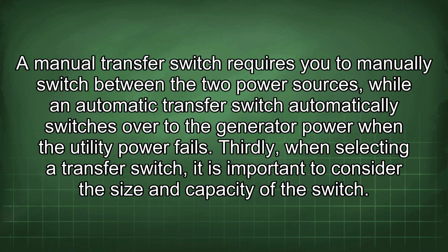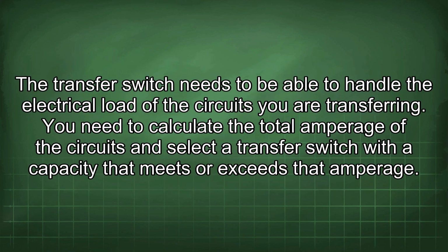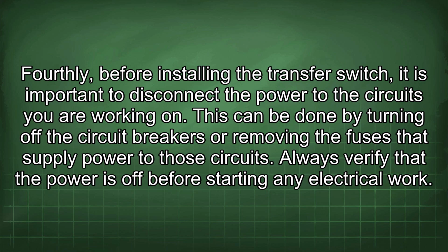Thirdly, when selecting a transfer switch, it is important to consider the size and capacity of the switch. The transfer switch needs to be able to handle the electrical load of the circuits you are transferring. You need to calculate the total amperage of the circuits and select a transfer switch with a capacity that meets or exceeds that amperage. Fourthly, before installing the transfer switch, it is important to disconnect the power to the circuits you are working on. This can be done by turning off the circuit breakers or removing the fuses that supply power to those circuits. Always verify that the power is off before starting any electrical work.